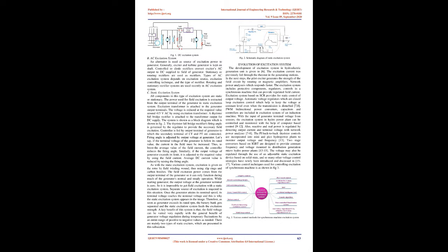Constant power factor regulation, AVR, and constant reactive power regulation are some control functions that may be applied to excitation systems. In power system stability analyses, when the nature of synchronous machines is to be effectively modeled, it is important to model their excitation systems in precise detail. The required models must be sufficient to reflect the overall performance of the excitation equipment for large, extreme disturbances as well as for minor disturbances.